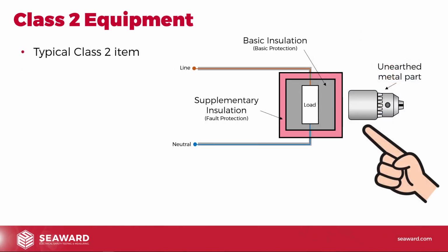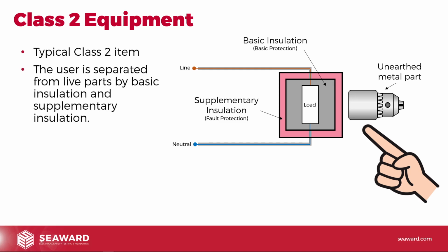So Class 2 equipment. What we've got here is a diagram of a typical item of Class 2 equipment, a Class 2 drill, for example. The user is separated from the live parts by basic insulation and supplementary insulation. What you can see here is we've got unearthed metal parts: a metal drill chuck. The chuck of the Class 2 drill is metal, but it's not earthed. It doesn't need to be earthed because it's separated from the live parts by 2 layers of insulation.